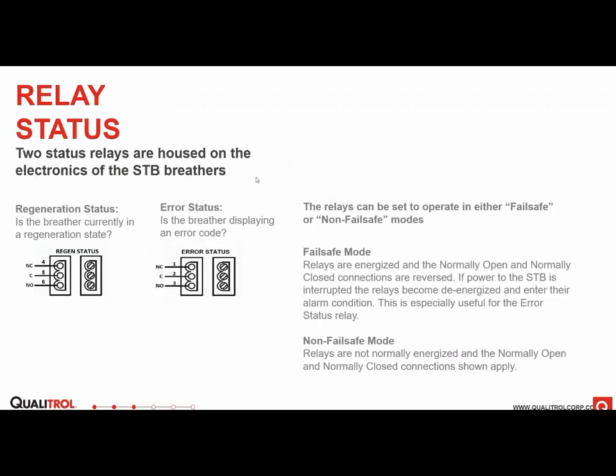So here are the 2 relays that are standard on every breather. Both of these relays are Form C contacts. One is for the regeneration status of the breather. So is the breather currently in a regeneration state? Is it regenerating? That's the regeneration one. And then the error status: is the breather displaying any error code? That can be anything from a Modbus error or anything. So you'll get a relay closed if there's any error, any abnormal condition with the breather.